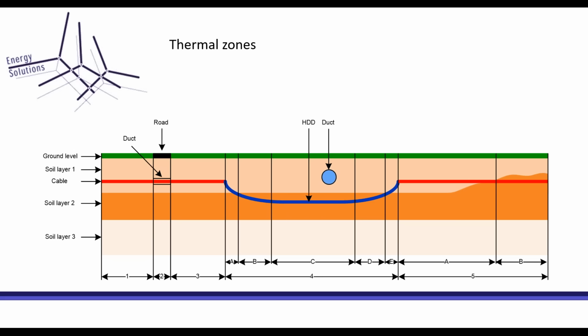So the thermal zones can be every zone where the cable is different; you need to model it as a separate zone. For example, if you have a road crossing where the cable is installed in a duct, you need to make a different zone. If it's in a horizontal drilling, you need to make a different zone. So all these zones you need to take into account when you make a thermal model for the complete cable connection. And it can be even only a zone of a few meters, because every few meters can be critical in the cable connection. So you can have overheating of the cable only on a very small part, and that's then the weakest link. So it's very important to model everything correctly.